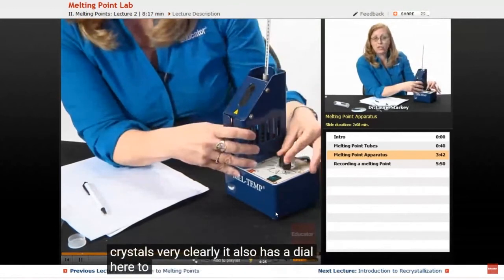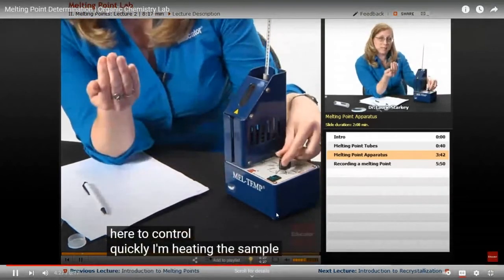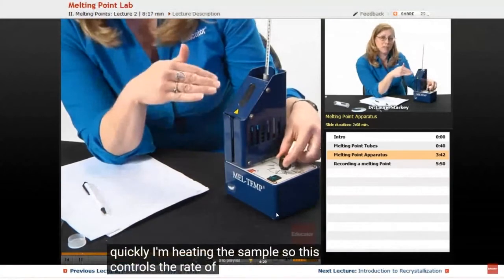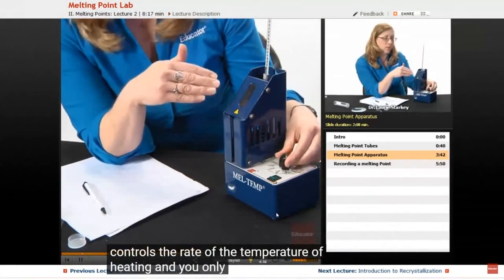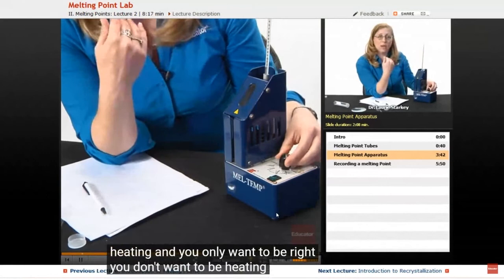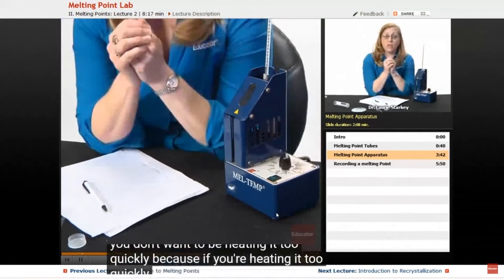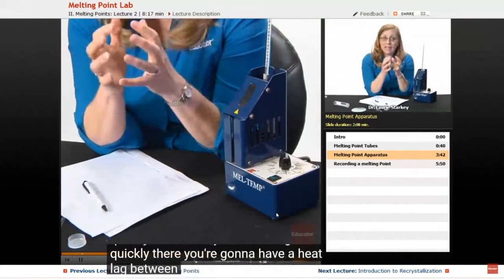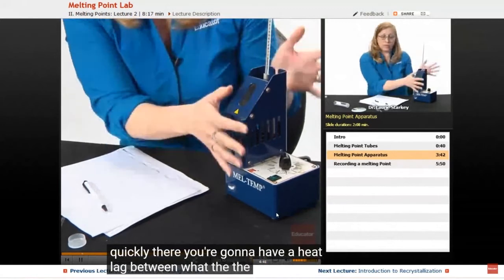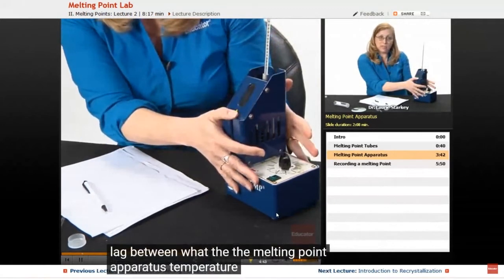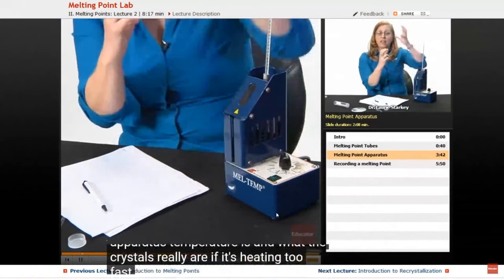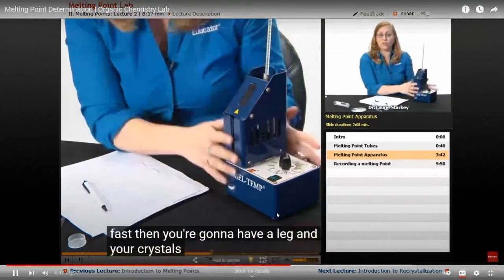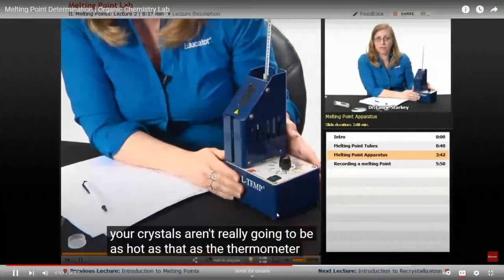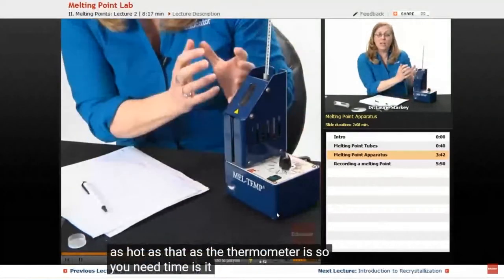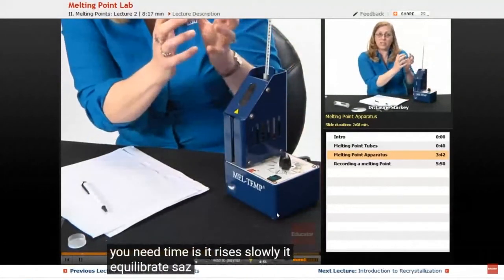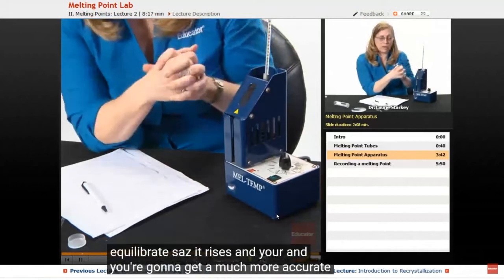It also has a dial here to control how quickly I'm heating the sample. So this controls the rate of heating, and you don't want to be heating it too quickly, because if you're heating it too quickly, you're going to have a heat lag between what the melting point apparatus temperature is and what the crystals really are. If it's heating too fast, then you're going to have a lag, and your crystals aren't really going to be as hot as the thermometer is. So you need time. As it rises slowly, it equilibrates as it rises, and you're going to get a much more accurate reading.